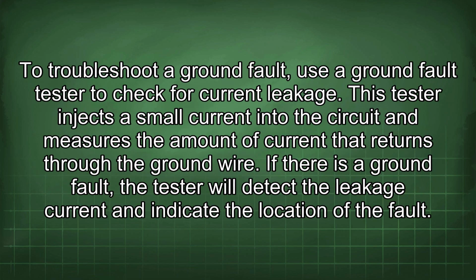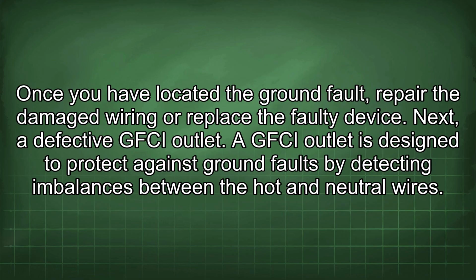To troubleshoot a ground fault, use a ground fault tester to check for current leakage. This tester injects a small current into the circuit and measures the amount of current that returns through the ground wire. If there is a ground fault, the tester will detect the leakage current and indicate the location of the fault. Once you have located the ground fault, repair the damaged wiring or replace the faulty device.